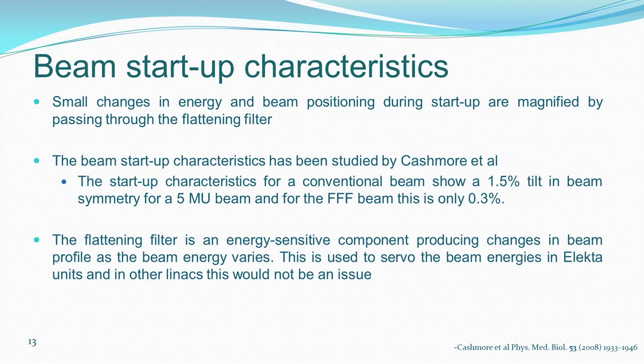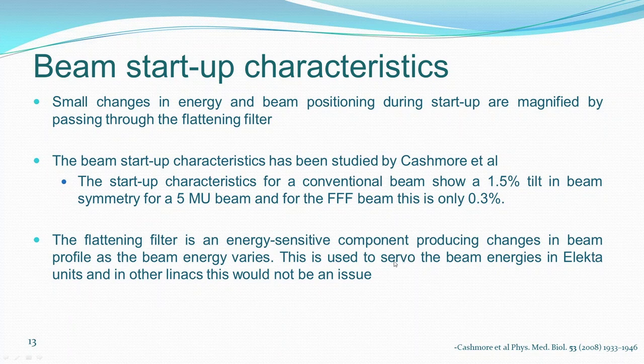Beam startup characteristics: when doing IMRT with small MUs, we were worried about startup characteristics. Small changes in energy and beam positioning during startup are actually magnified if you have a flattening filter. Without a flattening filter, this effect is much lower. A conventional beam shows about 1.5% tilt in beam symmetry for a 5 MU beam, whereas a Triple F beam shows only 0.3%. The flattening filter is an energy-sensitive component; Elekta even uses it for beam energy servo-control, so one must be mindful of that.